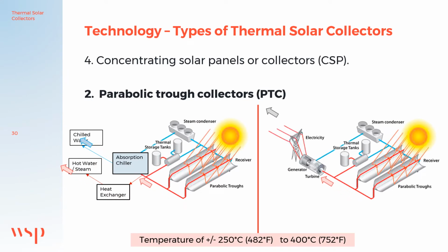PTCs can generate heat up to 400 degrees C or 752 degrees Fahrenheit, and are ideal to drive large district cooling and heating plants, where the heat will energize absorption chillers to generate chilled water or ice making, or to provide heating for water or steam, as shown in the picture on the left. The heat is also sufficient to generate electricity.